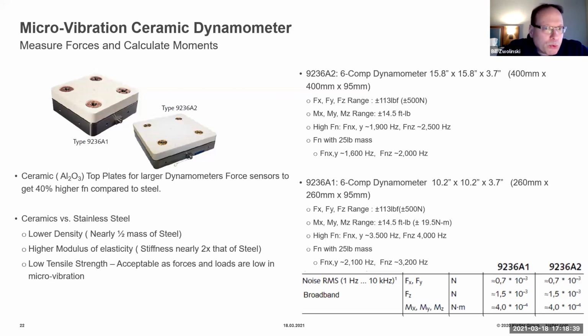It's really the right way to go when you're trying to get a large platform and measure very small forces. As we show here, the basic resolution of some systems like this is on the order of a millinewton in terms of broadband noise, and about 0.5 millinewton meter, also broadband noise, for moment or torque. So very sensitive. And when you get into these applications, they certainly require paying attention to seismic events and all kinds of other events of the facility that could actually disturb the measurement when you're measuring such low levels of force and moment.